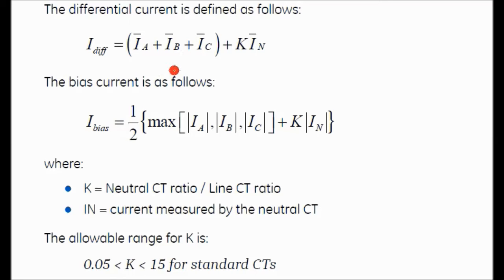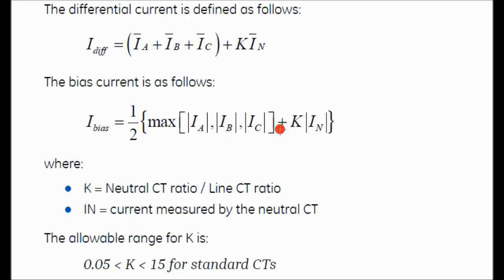During normal balanced load conditions, Ia + Ib + Ic equals zero, and since the current is balanced there is no neutral current, so In equals zero — therefore I_diff equals zero. The bias current equals half of the maximum of any phase current plus K × In, where In is again converted to the same ratio as the phase currents.